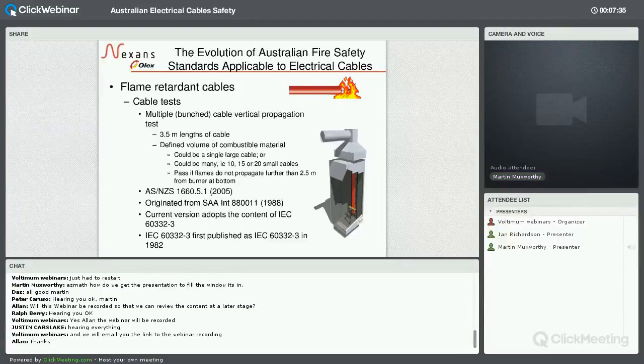The next test that we're going to look at is where cables are bunched together rather than a single cable. In this particular test, as detailed in AS1660 Part 5, Part 1, there's a defined volume of combustible material which you have to have, and there are different categories related to this test depending on the volume of combustible material. And as you could deduce, the more combustible material, the more fuel it adds to a fire, and the more difficult it is to stop flame propagating. So when you have lots of cables together on cable trays, it's a lot harder, and therefore to pass this test is more difficult than that first single cable test that I just mentioned. So you'd be typically looking at cables with, say, materials of higher oxygen index, for example.